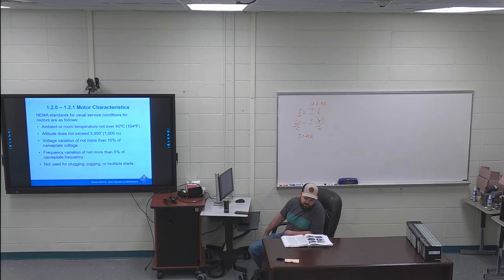121 motor service conditions. I've got the sentence before the bullet points highlighted. NEMA usual service conditions. Standard motors will perform in accordance with their ratings. And they have different ratings for different things. My highlight is, I've got the third bullet point highlighted. Voltage variation of not more than 10% of nameplate voltage. You can have a 10% variance of the nameplate voltage.